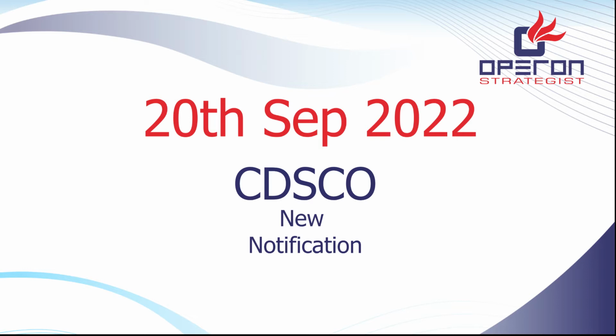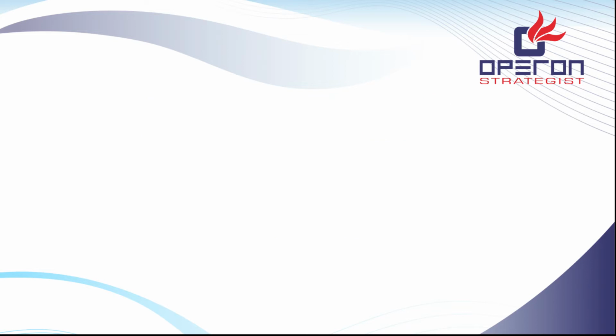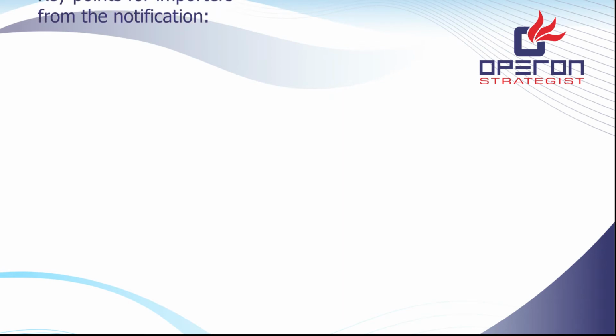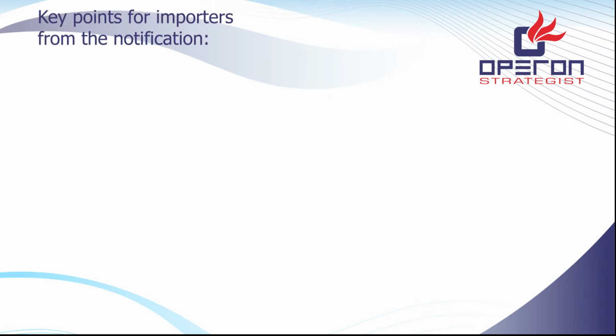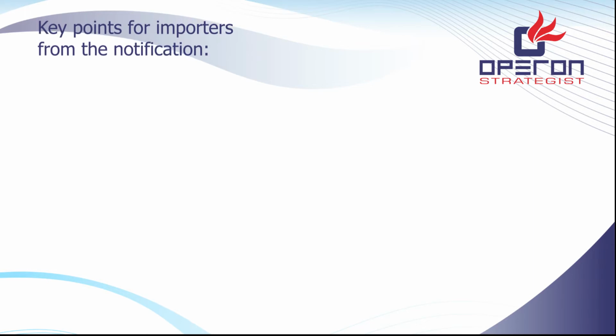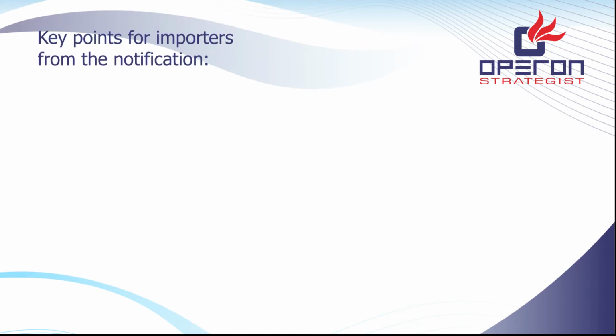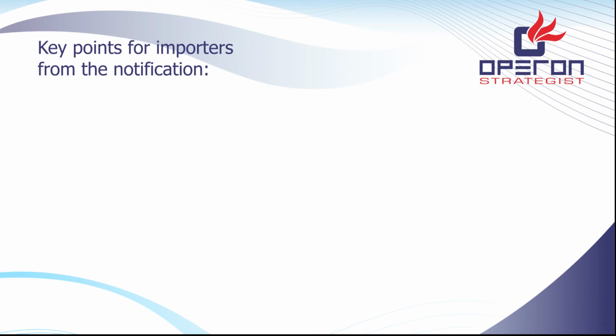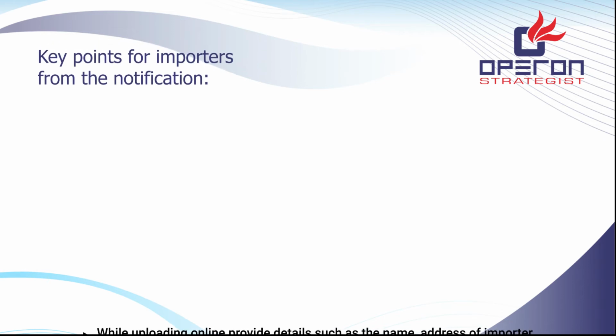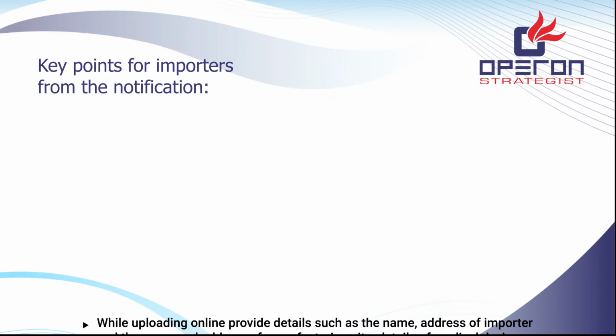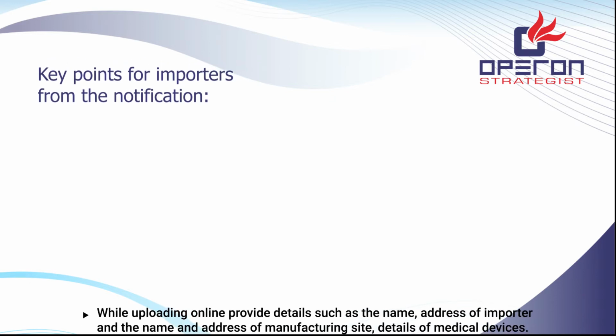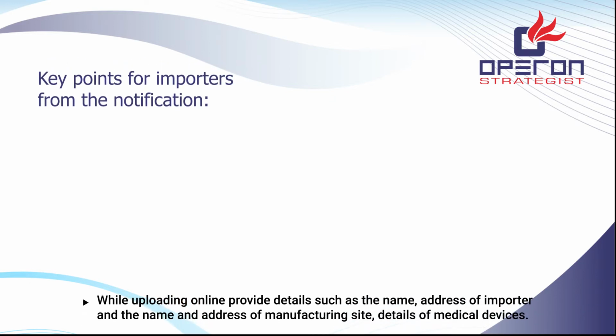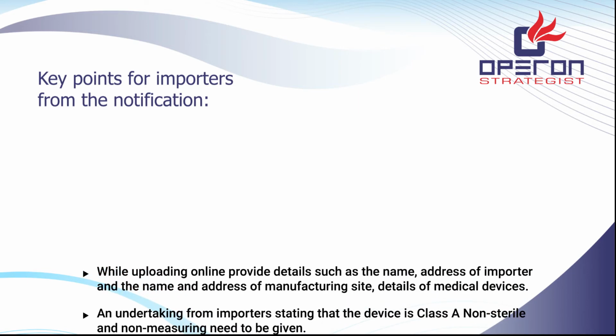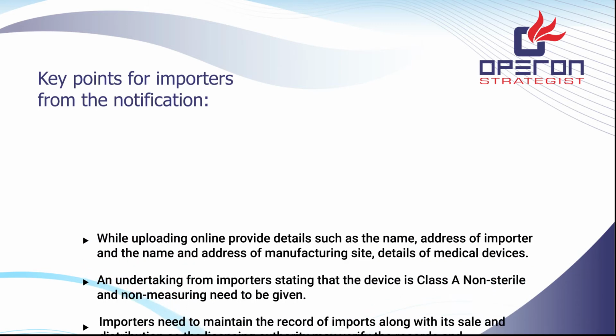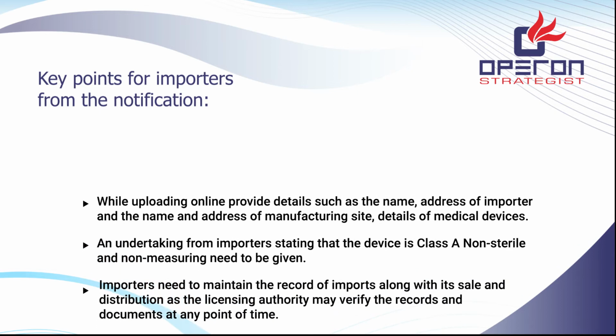So the requirements are as follows. Basically, you have to give the name and address of the importer and the name and address of the manufacturing site as a submission. You have to also provide details of the medical devices as required, and then an undertaking that it is indeed Class A, non-sterile and non-measuring, as well as an undertaking that the product conforms to the essential principle checklist of safety and performance, and also you have to self-certify that you follow the standards prescribed in Medical Devices Rules 2017.